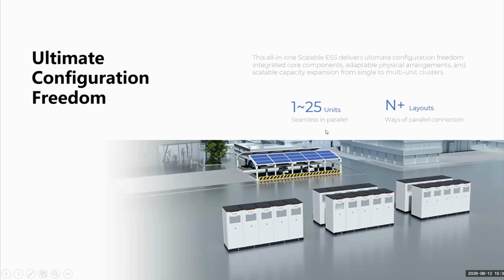And for parallel operation, in purely on-grid mode, meaning the grid will never black out, it can support 25 units. And some projects need the on-grid to switch to off-grid, or purely off-grid. This product can be paralleled up to 20 units. And for both of these connections we can support the seamless function.